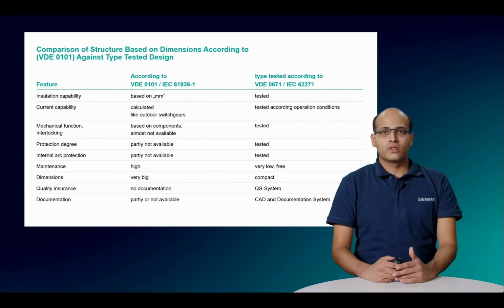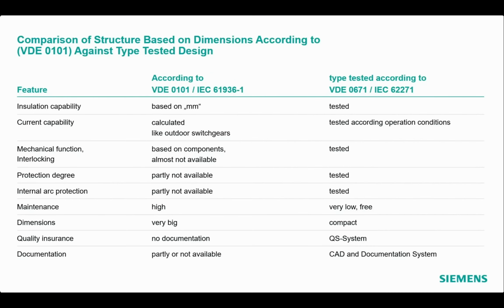Here is a comparison of the switchgear structure based on the dimensions according to VDE 0101 standard against that of a type-tested design according to IEC 62271 standards. On the first column, you can refer to the features. The middle column refers to the VDE 0101 standards, and last column refers to IEC 62271 standards.